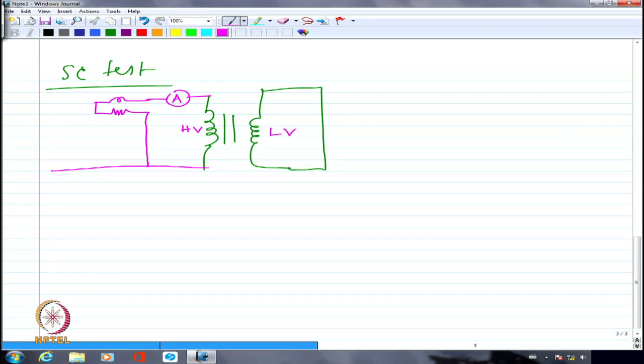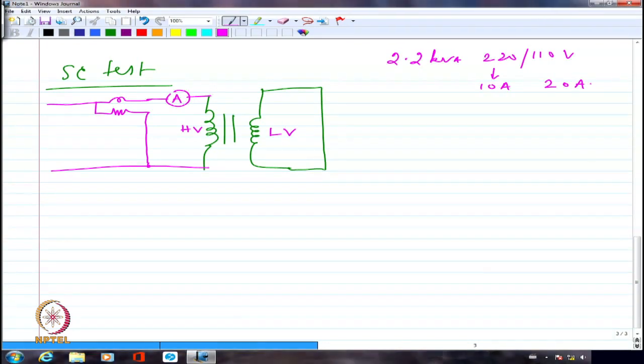See, if I am talking about again 2.2 kVA, 220 volts by 110 volts transformer, corresponding to 220 volts, I have only 10 ampere as the rated current. Whereas for this, I have to look for a 20 ampere source if I want to push rated current through the winding. Right? I am connecting the source on the HV side, so my source has to pump in only 10 ampere, not 20 ampere. So I'm always looking at lesser amount of value being applied, whether it is current or voltage, from my source. So in this case, I'm not going to apply rated voltage anyway. I'm going to apply only rated current. So where is the less value of rated current present? That is only present in the high voltage side. So I am using the high voltage side for energizing.